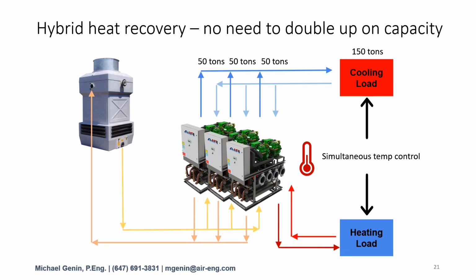In this instance, the cooling load is 150 tons, but unlike before, we have an installed capacity of only 150 tons rather than 200 tons like with the main chiller. This is one of the benefits of a hybrid system. Because it can reject to either the cooling tower or the heating load, you can count on its capacity even when the heat load becomes intermittent. You're not paying for a 150-ton main chiller plus an additional heat recovery chiller. You're only paying for a total installed capacity of 150 tons.